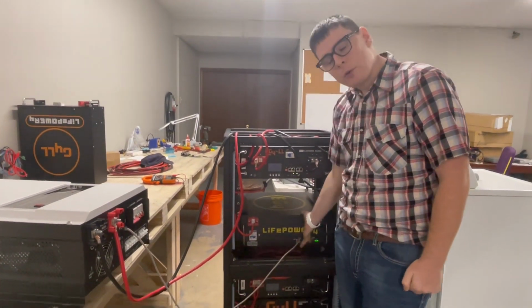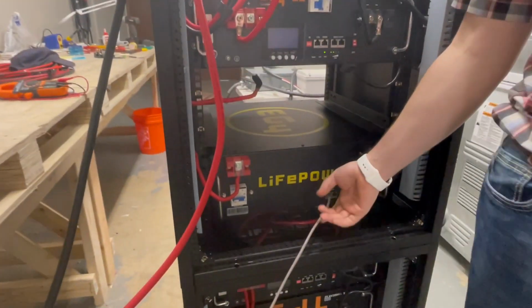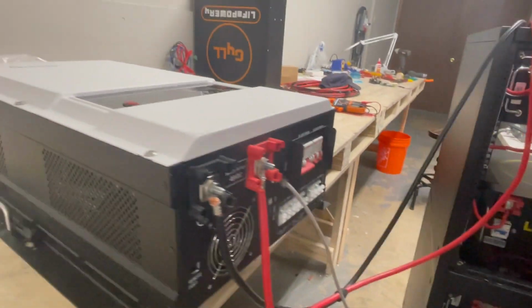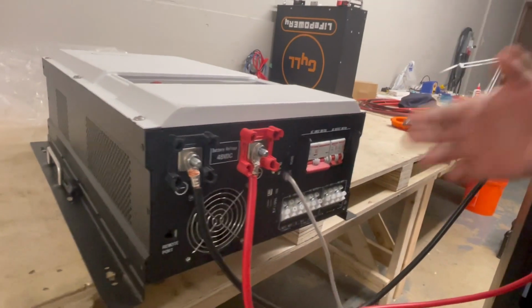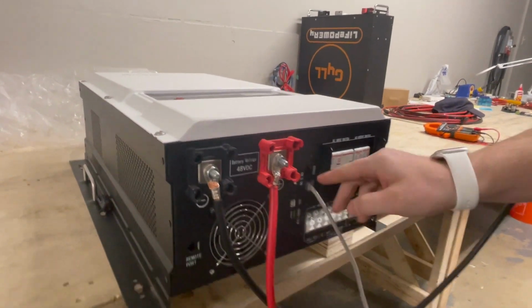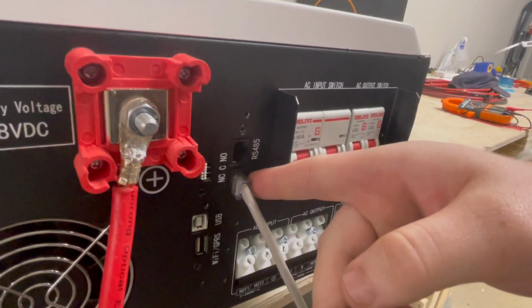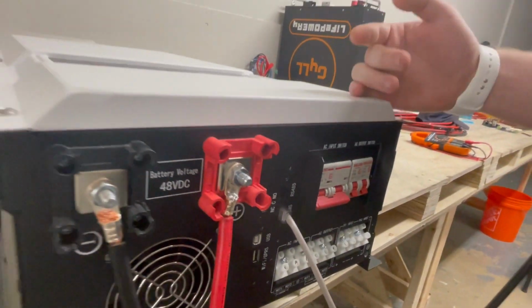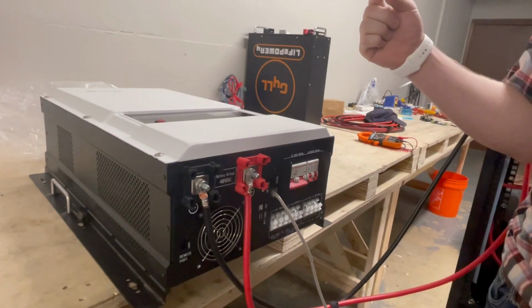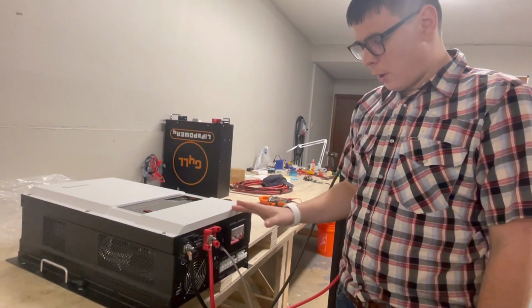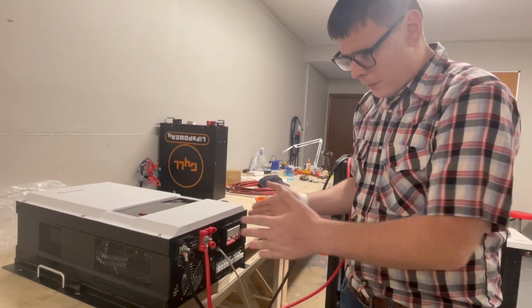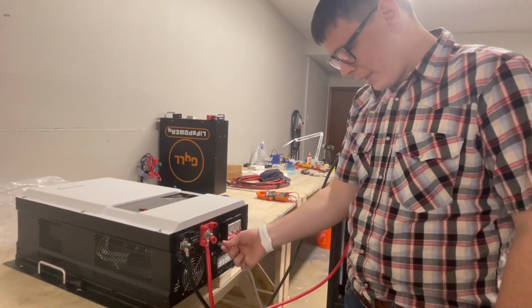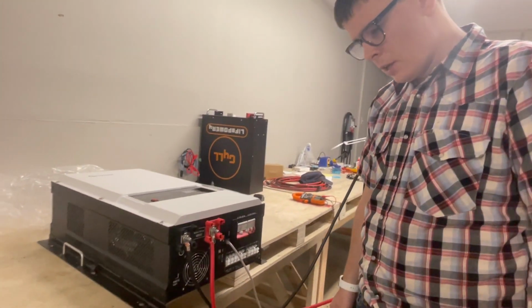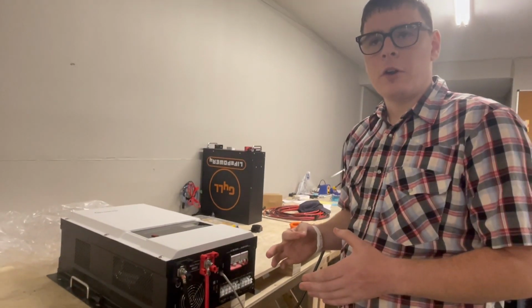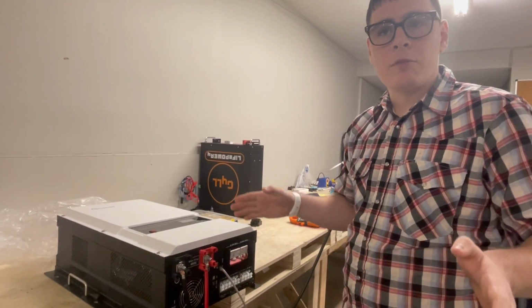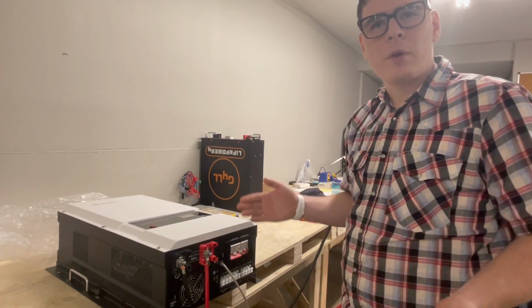So anyway, I've got the battery powered on right now, and we're gonna communicate into the 12 kilowatt Growatt inverter. Now, the 12 kilowatt versus the 5 kilowatt have a couple different ports going into them. The 12 kilowatt says BMS and RS-485. On the 5 kilowatt, you're gonna see CAN and RS-485. For the 12 kilowatt and 6 kilowatt inverters of their class, the transformer type, you're communicating with the BMS port. For the 5 kilowatt inverter and any of the other stackable inverters, you are communicating with the RS-485 port.